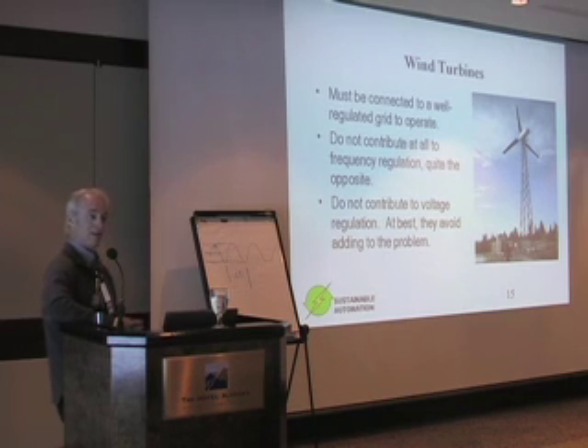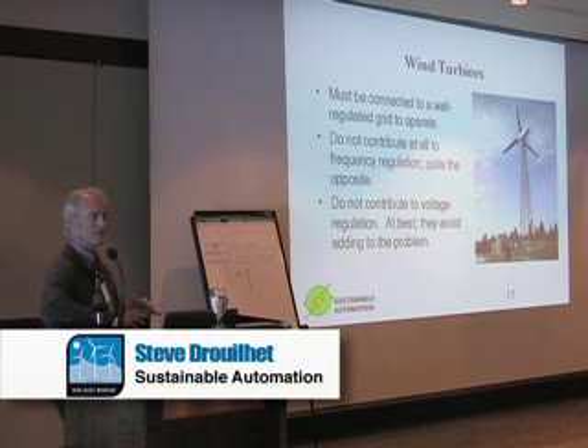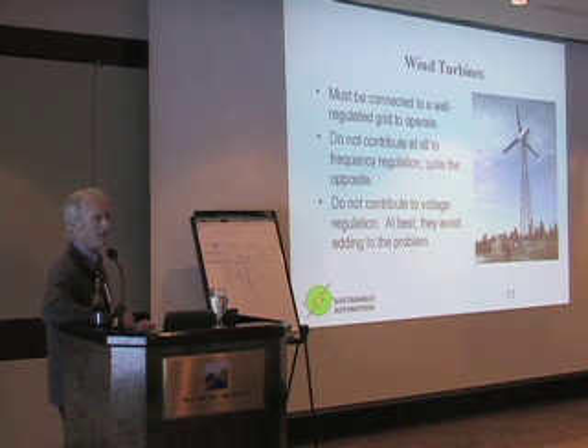Wind turbines don't contribute to voltage or frequency control. They require, again, as Russell pointed out, a fairly well-regulated grid to connect to. Most of these machines that we deal with in the village power projects were not designed for wind diesel applications. They're designed to be connected to the grid, so that's what they expect to see, a well-regulated frequency and voltage. And if you deviate from a fairly narrow band of frequency and voltage, they won't operate.